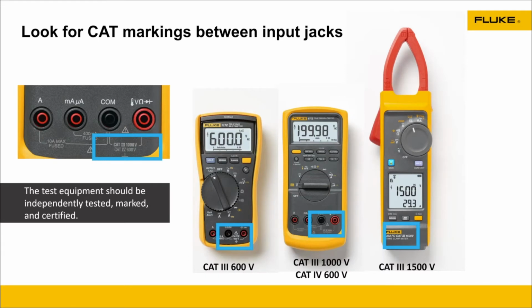How do you find those markings? Again, most DMMs, whether it's Fluke or others, should have somewhere on the meter the category rating that it is for. You can see here on the input jacks on the left, this was rated for category 3 1000 volt, category 4 600. And even some meters can handle a category 3 600. So again, know where that is on your meter, look for it. It's just more knowledge that will make you safer out in the field. Speaking on that solar side of it, and higher energy, higher voltages, we now have a category 3 1500 volt rated clamp meter. Again, it's all about that safety and being out there.